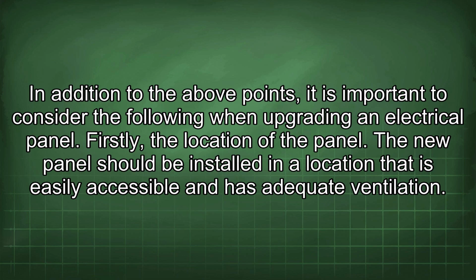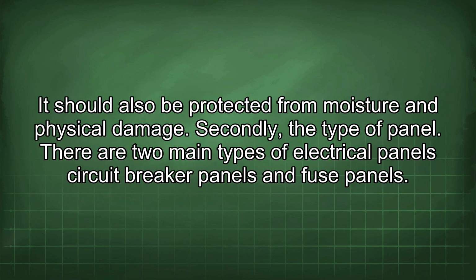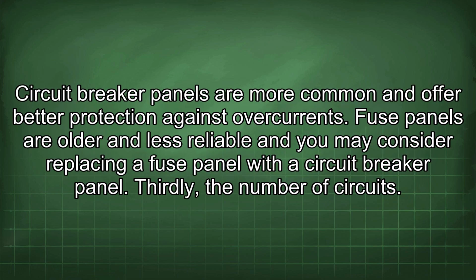Firstly, the location of the panel. The new panel should be installed in a location that is easily accessible and has adequate ventilation. It should also be protected from moisture and physical damage. Secondly, the type of panel. There are two main types of electrical panels: circuit breaker panels and fuse panels. Circuit breaker panels are more common and offer better protection against overcurrents. Fuse panels are older and less reliable, and you may consider replacing a fuse panel with a circuit breaker panel.